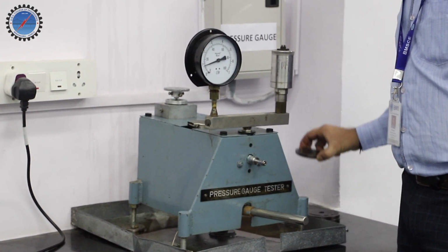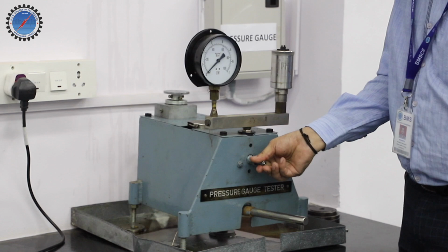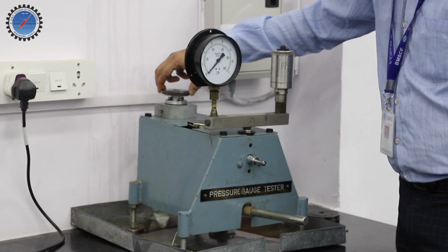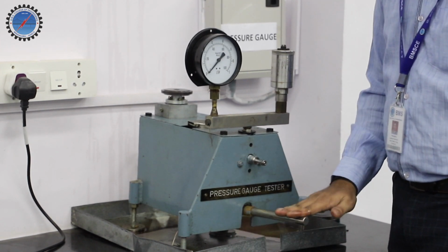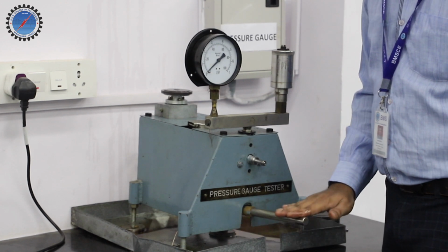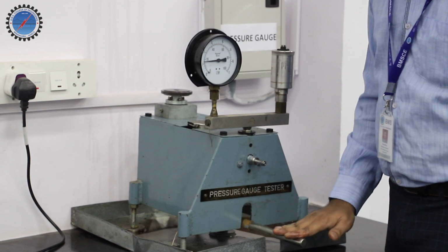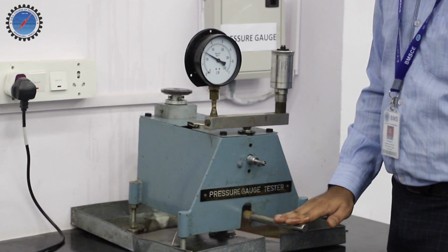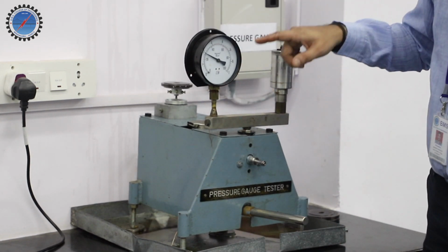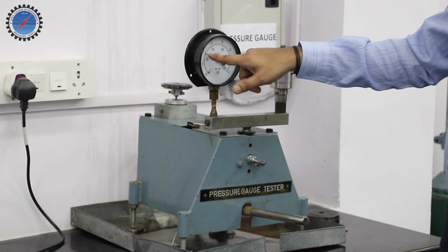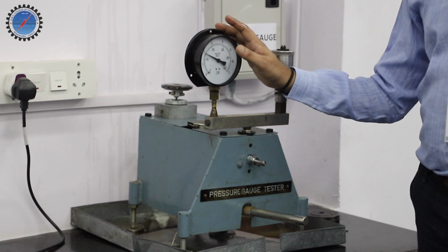Now I am loading one more ATA to show you how it will work. I am releasing the valve and loading another 1 ATA here. I am locking the release valve here. If you build a pressure here, you can see it gradually increasing the reading on the Bourdon tube pressure gauge, and whenever the weight is lifted, the pressure built in your system is equal to the load acting on it. It is giving 1.8 kg per centimeter square, but actually we loaded 2 kg per centimeter square. That is the error in your Bourdon tube pressure gauge.